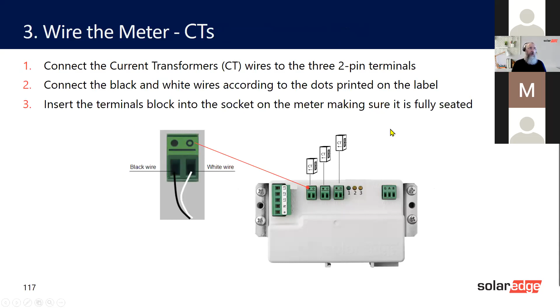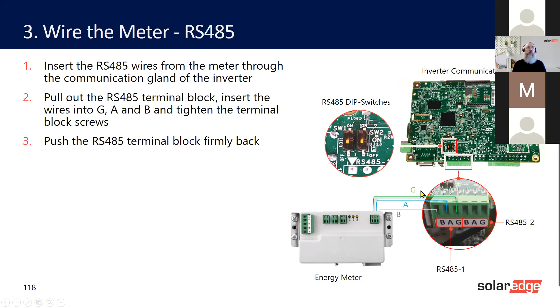And here again is the communication board that we spoke about. Here are the dip switches. Here are the RS485 connections you can see. Now you can have any of them. It doesn't matter which one you put your meter or your follower and leaders in, as long as you set the dip switches. There are only 2 products that I know of that must have a specific place. For the EV charging inverter, you must connect the meter to RS485-1. For the single phase storage inverter, not the one we're looking at today, you must use RS485-1.